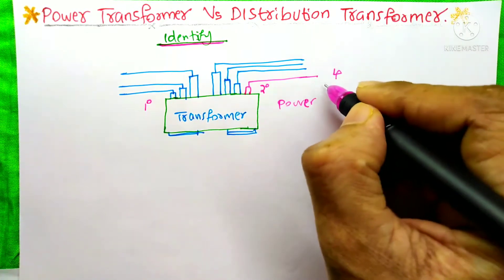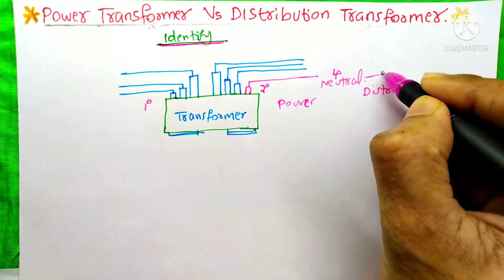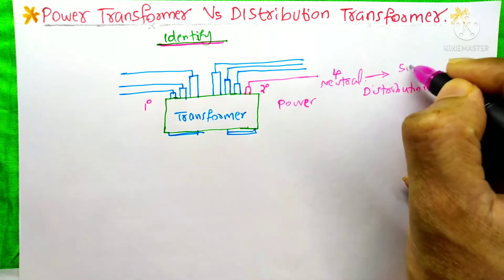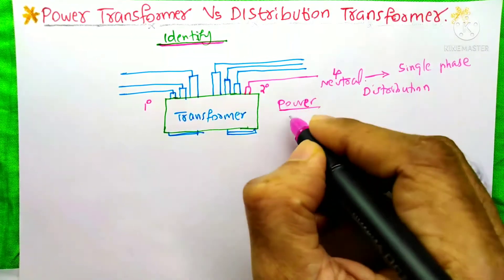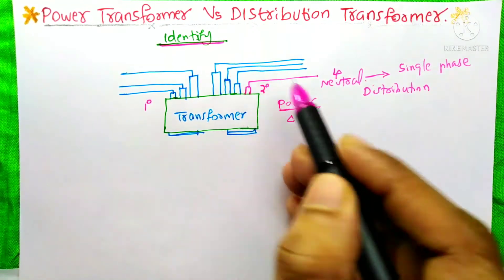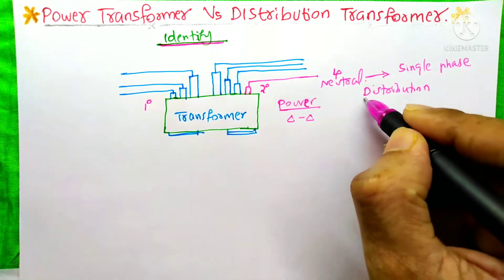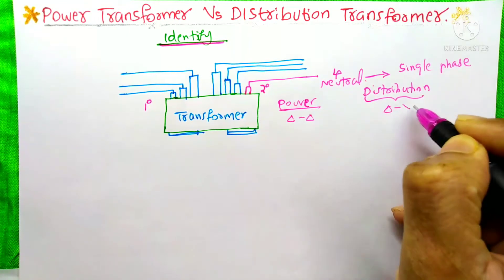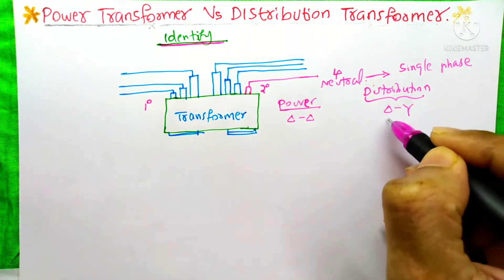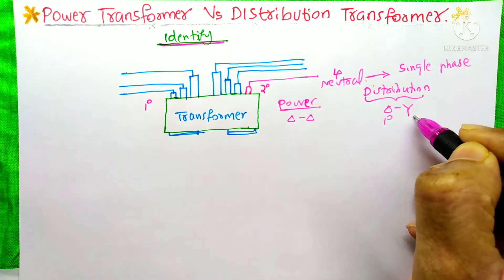This fourth conductor is the neutral, and this neutral is used for single-phase loads. The power transformer is always delta-delta configuration — three conductors on the primary and three conductors on the secondary side. The distribution transformer is always delta-Y — three conductors on the primary side and four wires on the secondary side.